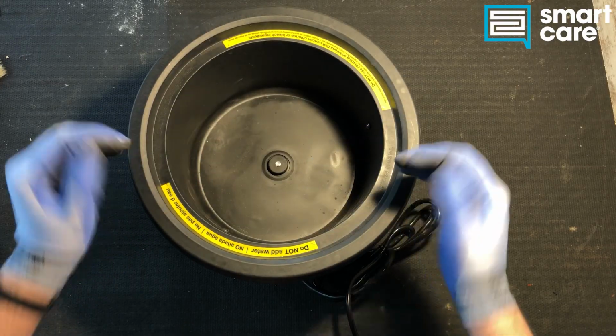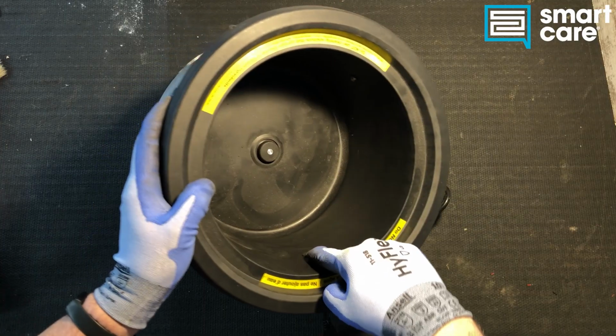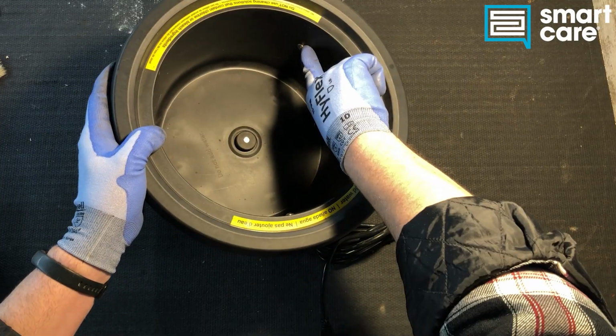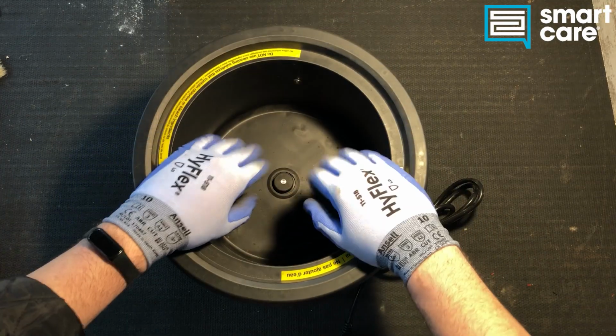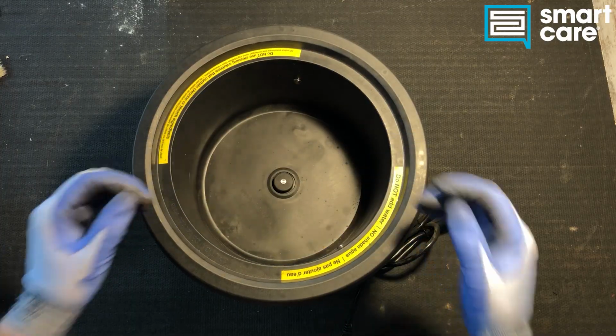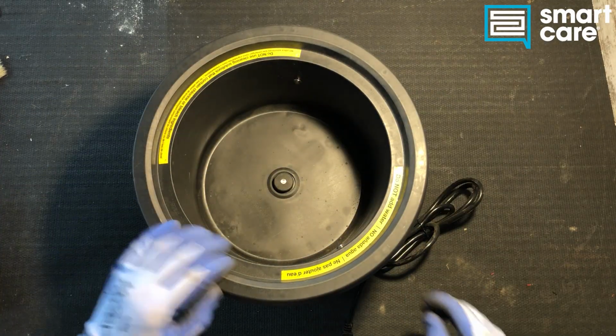Because of that high efficiency, it's really important that we monitor temperature. So I'm guessing we're going to find that these little studs are temperature probes to make sure the actual pot doesn't get too hot, since we could potentially put a ton of heat energy into it.